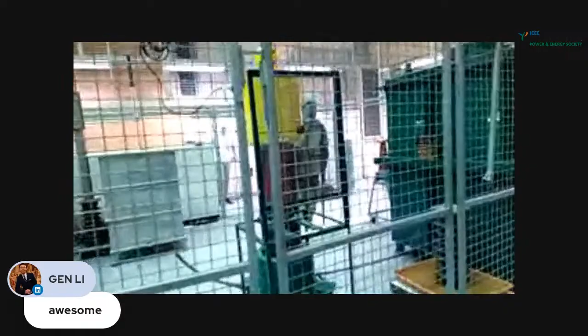So what's very interesting here, what we have seen, is that the discharges occurred on the surface of the insulator. They came here along very, very long way, despite there was this very thin glass between the high voltage and the grounded part. And the reason for this is that the surface of the insulators is always the weak spot because of contamination, because of moisture. It's always much, much weaker, by orders weaker than the material itself.